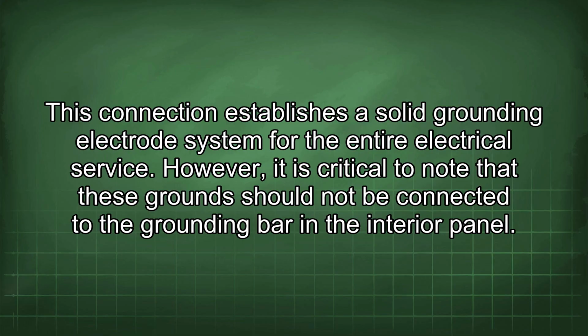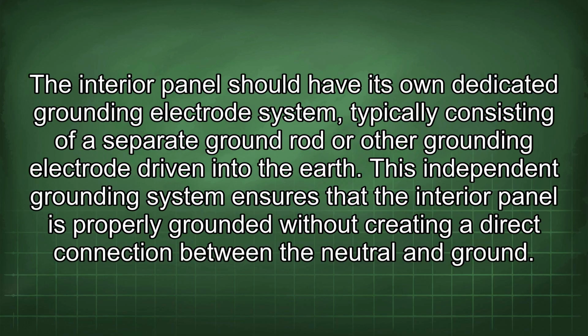However, it is critical to note that these grounds should not be connected to the grounding bar in the interior panel. The interior panel should have its own dedicated grounding electrode system, typically consisting of a separate ground rod or other grounding electrode driven into the earth.